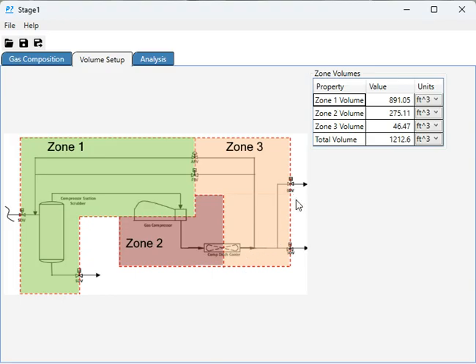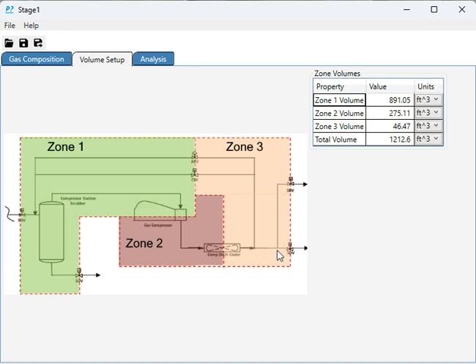Upstream, again, we're looking for the discharge check valve delineating this volume, also not shown. That's typically going to be somewhere downstream of the discharge cooler, maybe upstream or downstream of the shutdown valves.